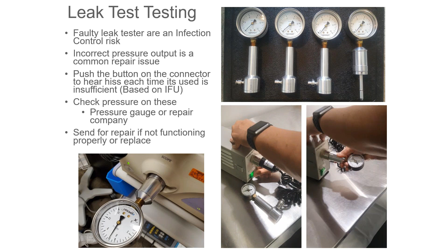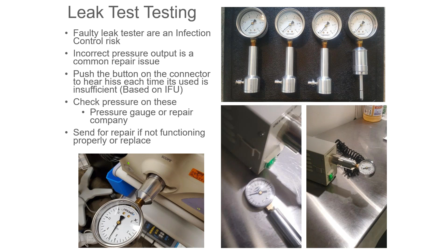This is the same unit. If you look at that, the first one we use with the attachment, the coil tube. And when you do that, you measure the output, to see how much pressure is put out. So this is about 4 PSI. So now let's attach it directly and get rid of that coiled wire. Sorry about all the noise, but that's what the CSPDs look like. But if you look at that directly, it's about 6 PSI. When you attach that coiled wire, you lose about 2 PSI. So when you have that 2 PSI drop in that small coil, what would happen if you attach that to a scope? Would you drop more pressure? And would you still be able to detect the leak?